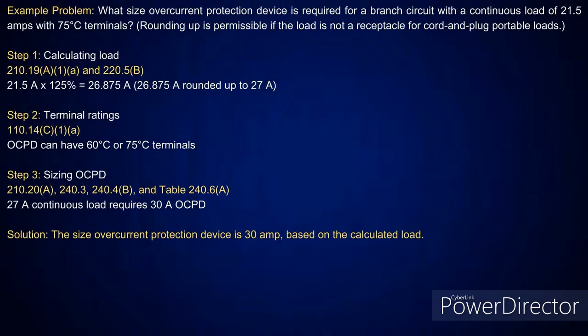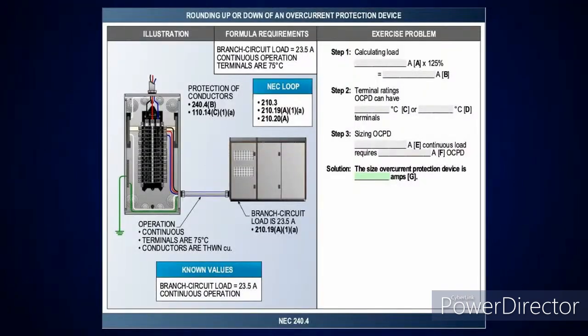You've got another one here. It'll be your problem. You have a branch circuit load of 23.5 amps. It's continuous. You take it at 125%, and then you're going to size off that. We tell you up in the formula requirements that the terminals are 75 degrees C. Okay? So, everybody, that'll be your exercise problem. You shouldn't have too much problem with that.